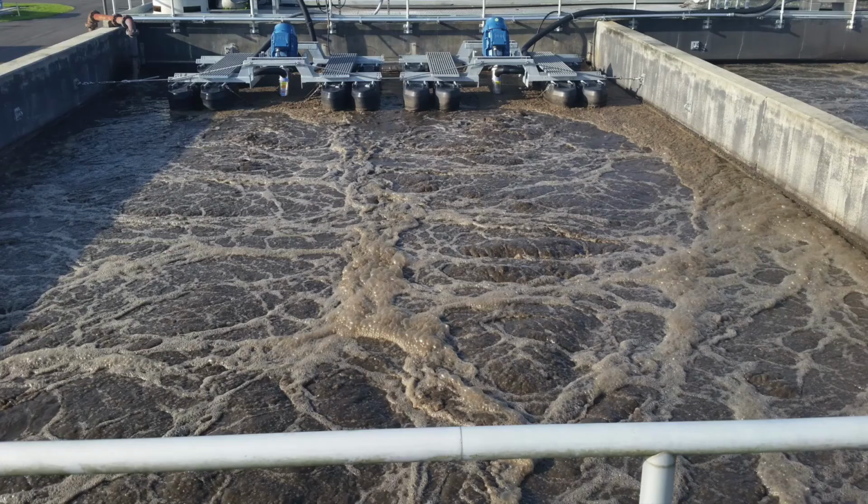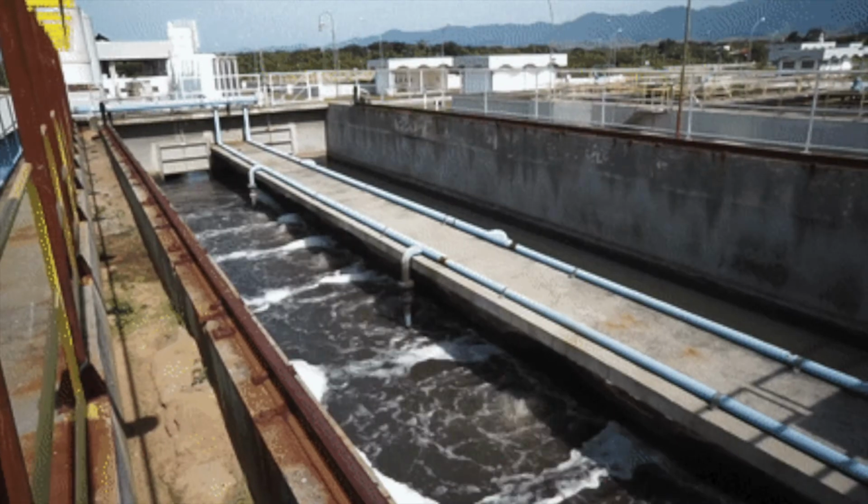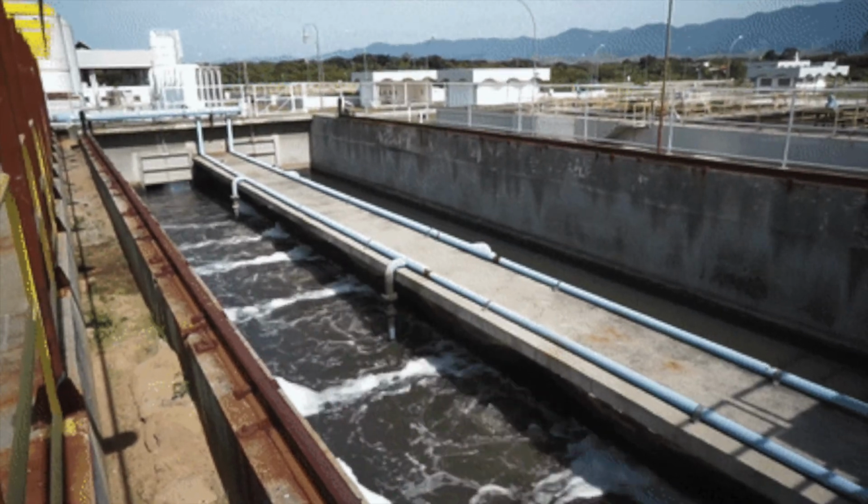Secondary treatment. Oxygen is added to water to aerate it and help the activated bacteria in the water to start breaking down the organic matter remaining there. The clear water now passes through filters again to remove any small sediments, living organisms, and chemicals.